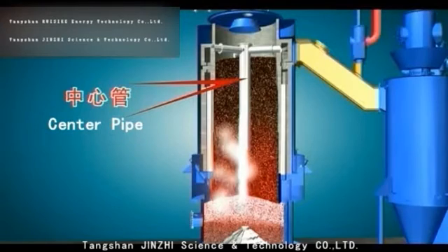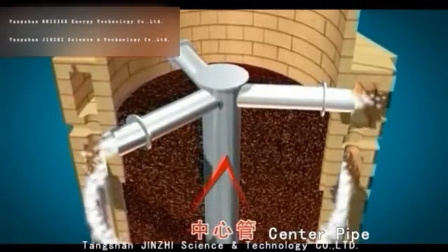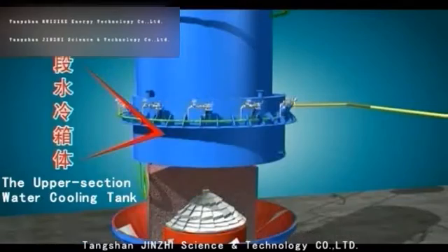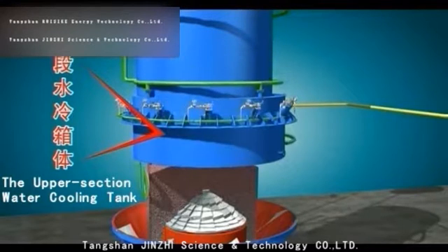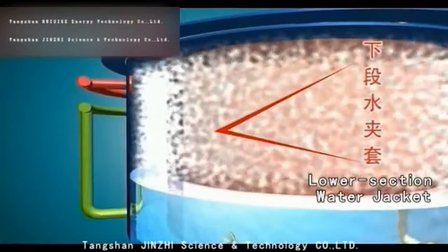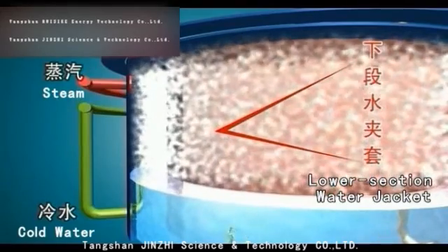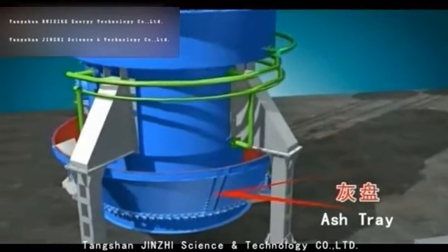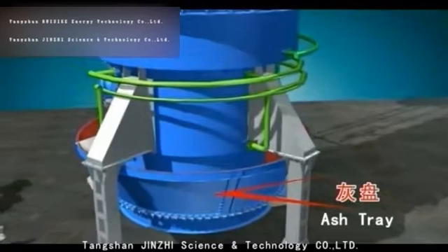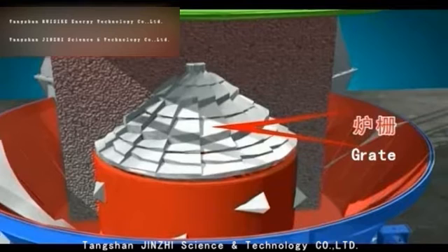This makes the system simple, resistant to high temperature, free of slag, long in life, and convenient in maintenance. The water cooling tank connects to the carbonization section to produce steam and meet the needs of the gas generation station. The water jacket structure is adopted to produce saturated steam, which can fully meet the demand of the furnace without external steam, so that the production cost is reduced. The furnace adopts a wet ashtray, high ashtray seal, and high gasification pressure operation, achieving large and stable gas generation volume.